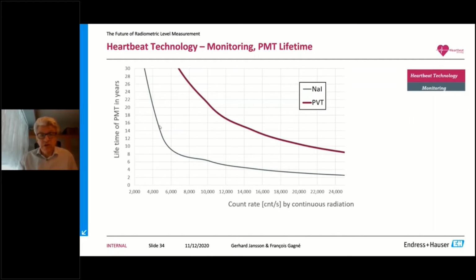There is one curve for the sodium iodide crystal, which is typically used in density applications, and the red curve is for the PVT that is used for switches, continuous measurement, interface, and also to some extent in density applications. So what this shows now is the relation between life expectation and the number of counts. If I have a relatively low number of counts, an average of like 10,000 counts, I can expect around 20 years of life expectation.